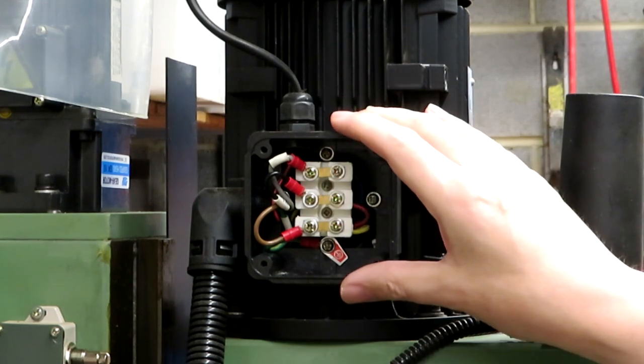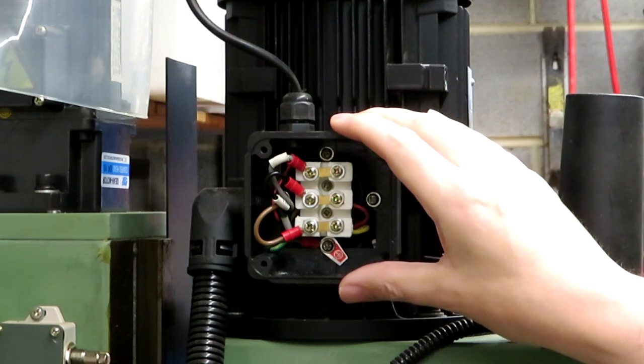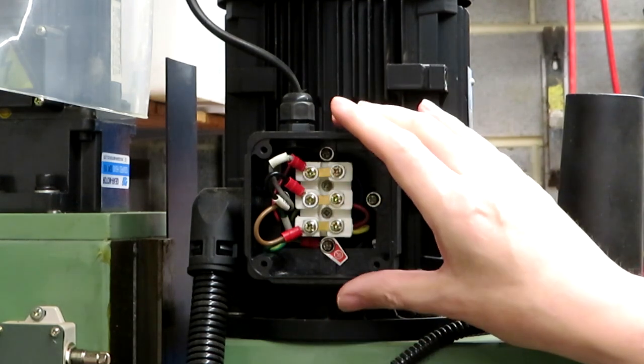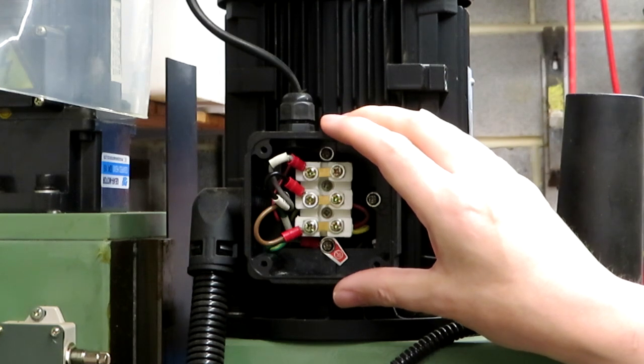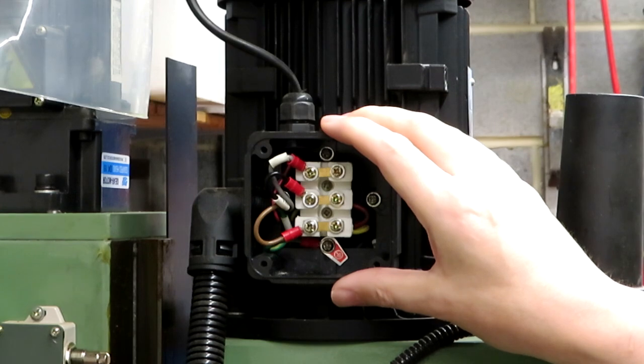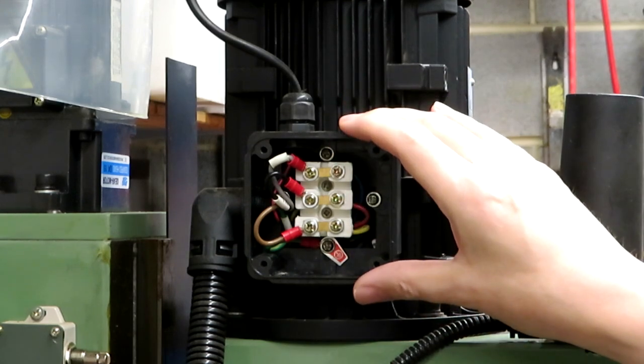Now, quite a lot of current measuring meters and voltmeters are actually expecting to see a sinusoidal waveform, and if they don't see a sinusoidal waveform, they can become quite confused and basically give you nonsense on the reading. The other thing that we would find is that because the supply is being chopped up, it looks very, very electrically noisy. So noisy, in fact, that a typical voltmeter or current meter would have trouble locking onto the true signal, and again it would just display nonsense.